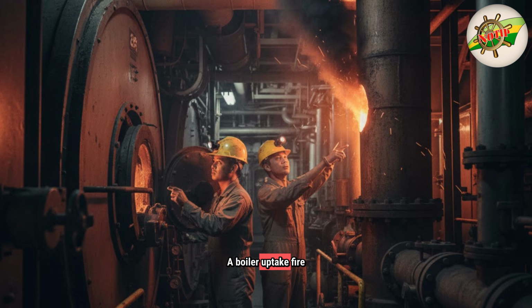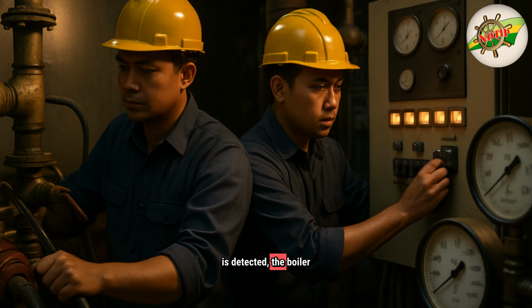A boiler uptake fire occurs when unburnt fuel particles and soot accumulate in the boiler's uptake or exhaust passages, igniting due to high temperatures. This happens when combustion is incomplete, often due to poor atomization, incorrect air-fuel ratio, or fouled burners. Once ignited, soot can burn intensely, heat metal surfaces to dangerous levels, and potentially lead to uptake explosion if gases accumulate. When an uptake fire is detected, the boiler must be handled with extreme caution.